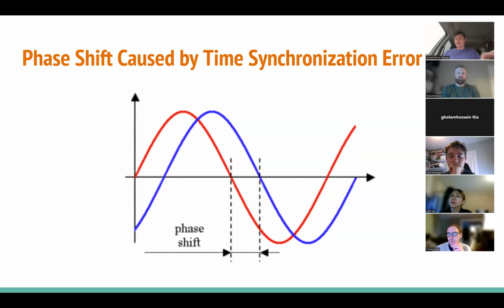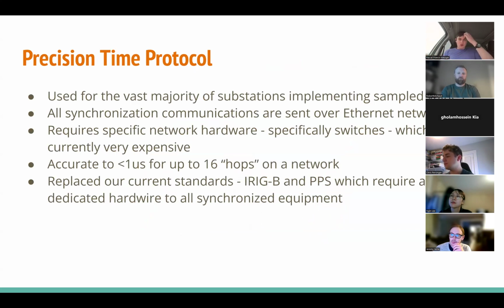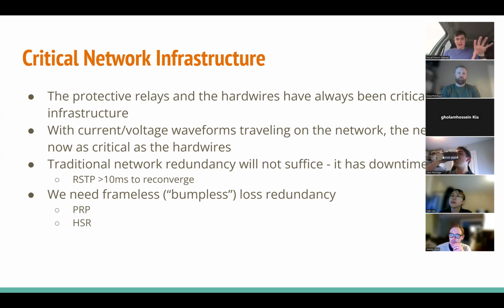So time synchronization is important for conventional substations, but incredibly important and much more complex for a digital substation. Along with that, the network in a substation has always been important, but in a conventional substation, if the network goes down for a few seconds or minutes, it's not good, but it's not the end of the world—your protection is still functioning. In a digital substation, as soon as the network goes down, even for one frame of Ethernet, you don't have protection during that time. That's why we care so much more about the network in a digital substation.